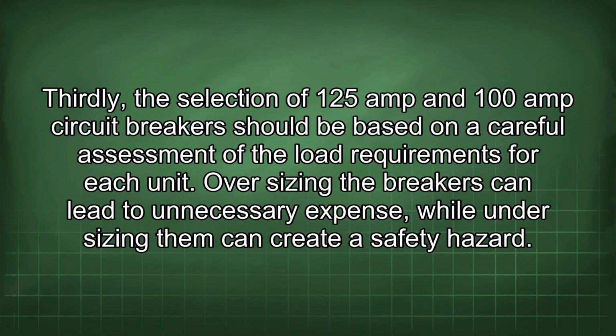Thirdly, the selection of 125 amp and 100 amp circuit breakers should be based on a careful assessment of the load requirements for each unit. Oversizing the breakers can lead to unnecessary expense, while undersizing them can create a safety hazard.